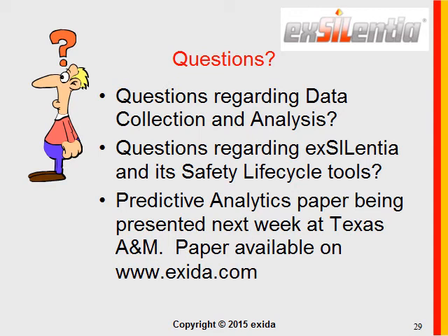The concept is, if you ask for a generic set of failure rate data, we have to assume it's one of the worst designs of the entire class. The worst design. We have to assume that. This is safety. So we will look at the predictive analytics statistics, and we will pick a value very close to the outlier result which you saw on a previous slide.